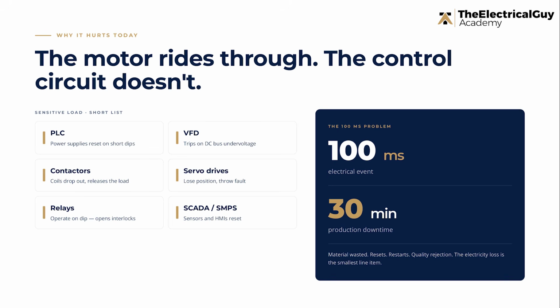A very short sag may not stop the normal motor immediately because the motor has inertia. But the control circuit feeding that motor may trip. The contactor coil may drop out. The VFD may detect undervoltage. The PLC power supply may reset. The relay may operate. And once the control system trips, of course the process will stop. This is the main problem. The main motor may be capable of riding through that disturbance, but the control system may not. And such kinds of disturbances happen in industry, especially if it is a process industry. The impact can even be bigger. The line may be stopped for several minutes to several hours, and that directly costs you money.